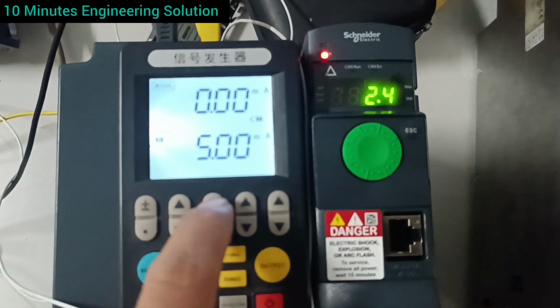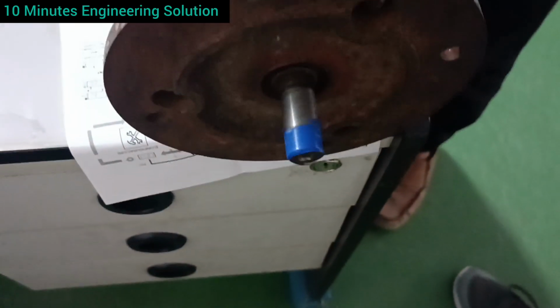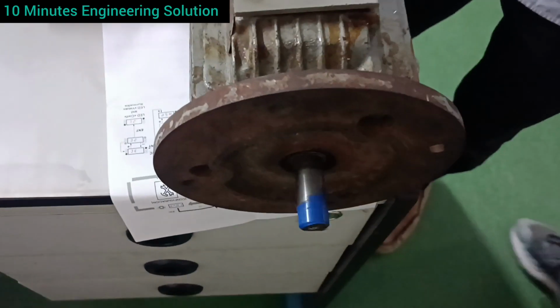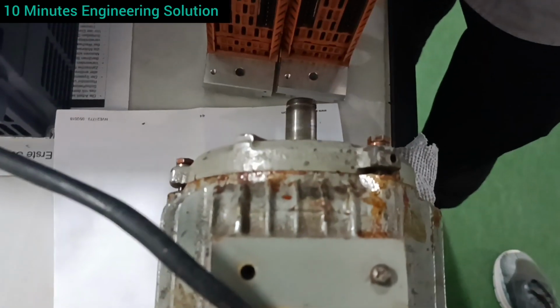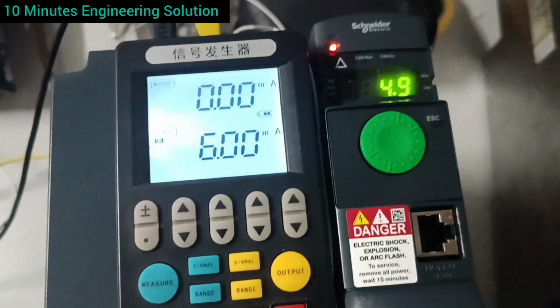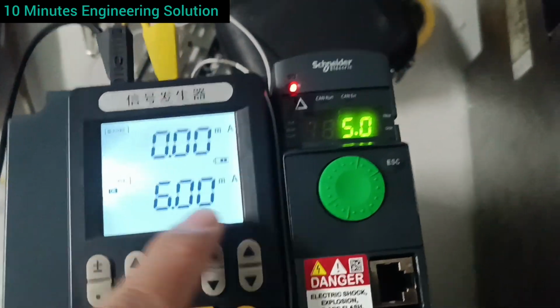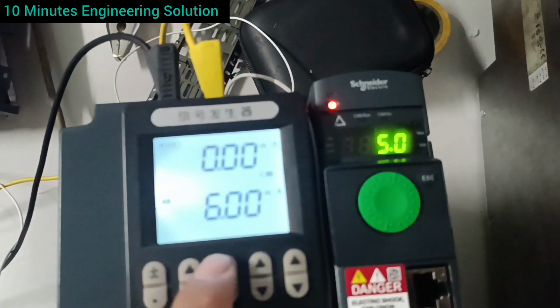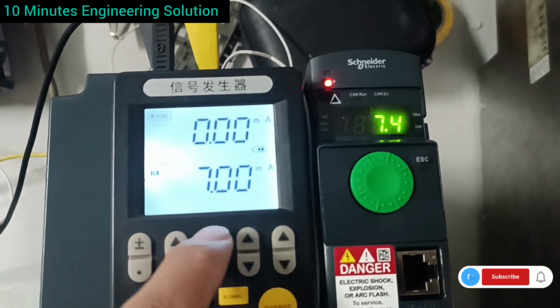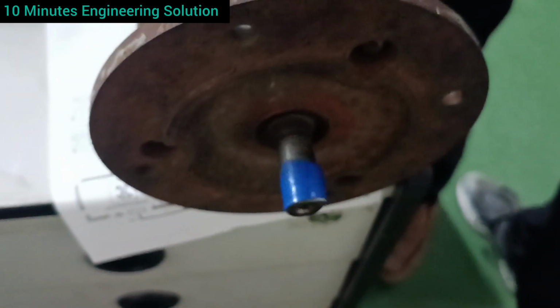If I increase again to 6 milliampere, you can see the VFD is increased and the motor speed is also increased. This is the analog signal functioning very smoothly. If I change the value to 7 milliampere, VFD speed is increased and motor speed is also increased. That means the full system is working very well.